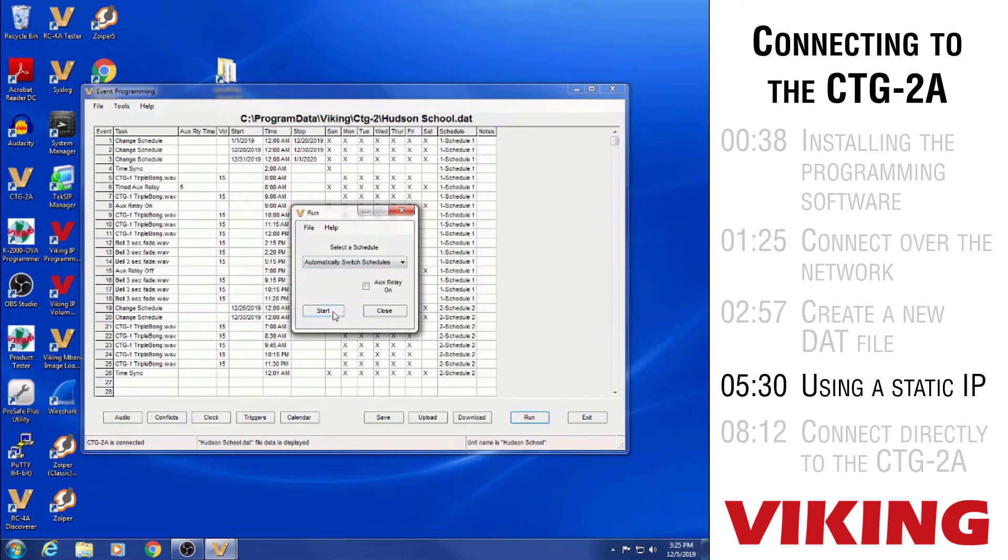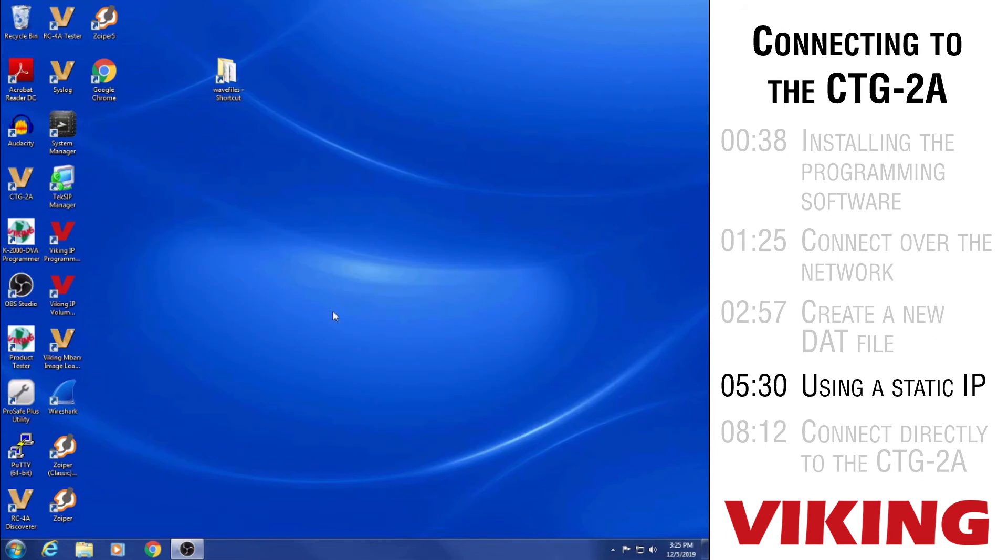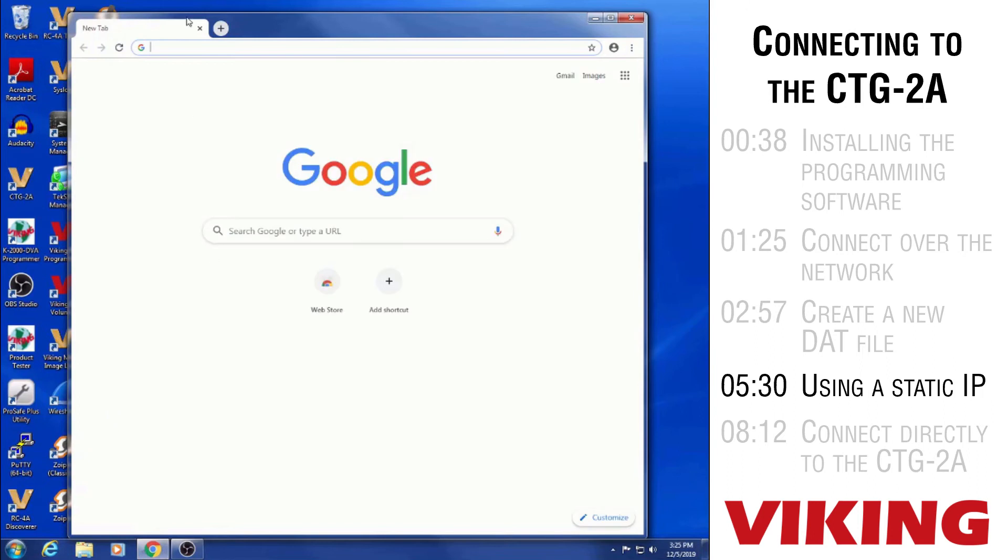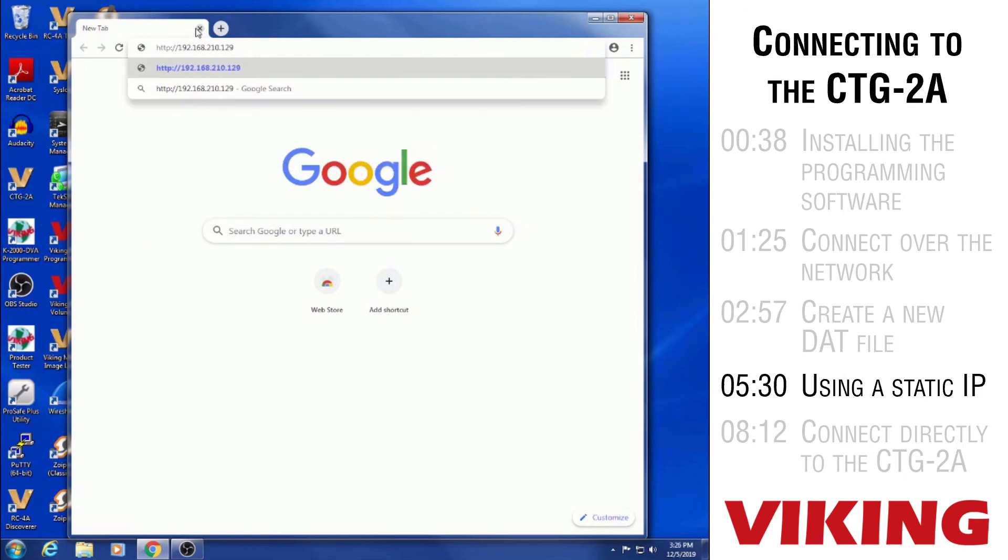The other method is using just a browser because the CTG-2A does produce a web page just for getting to the network settings page. So you can't do any event programming through the web page that it produces but it does allow you to actually connect to the CTG-2A to change anything that we just saw on that network settings page. So I noticed that on that connect screen when we were connecting to the CTG-2A with the CTG-2A program the 192.168.210.129 was the IP address for the CTG-2A.